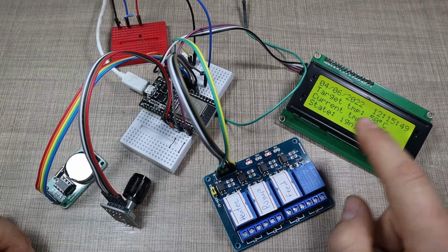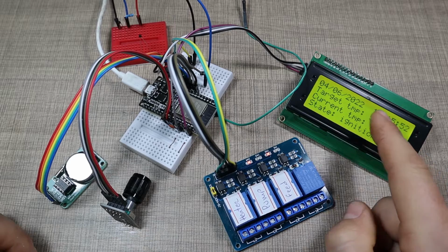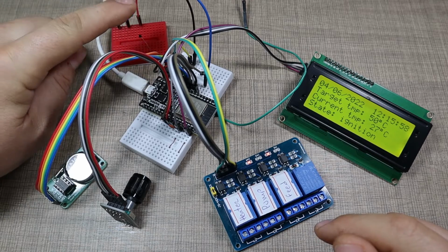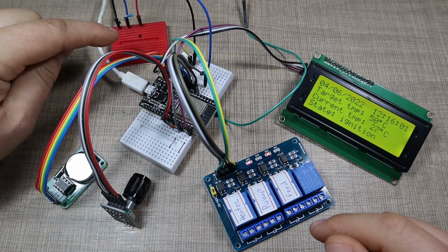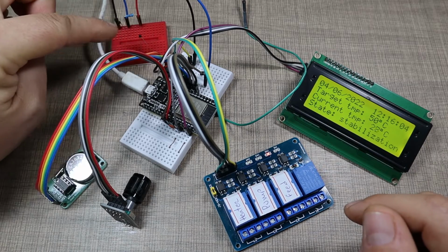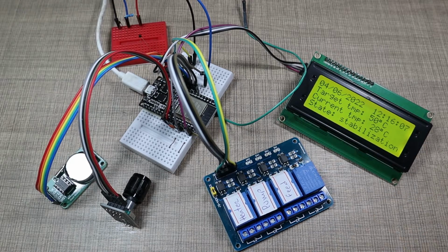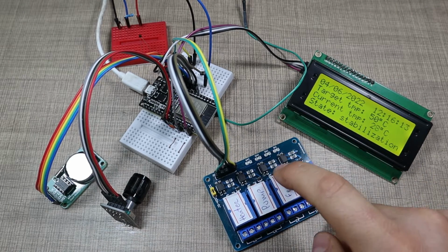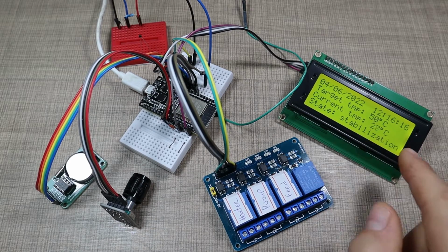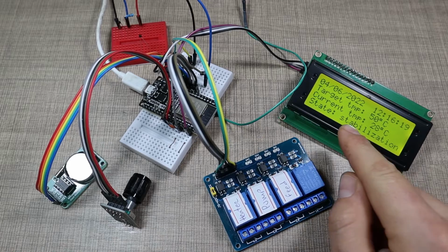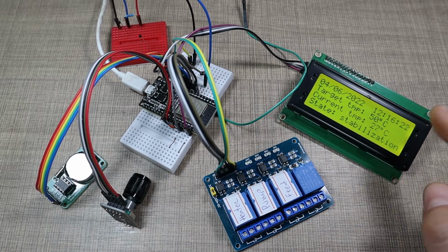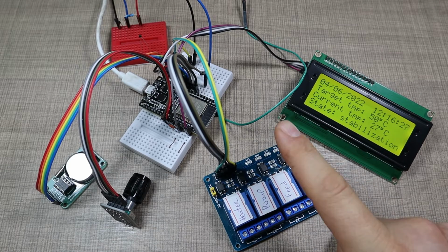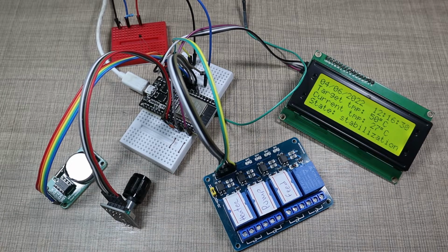So during the ignition time, the feeder will work for the set period of time, and then we'll have the heater. Ideally, we will also have a check for the temperature of the exhaust gases coming out of the heater, and that would control the period as well. Now we went into the stabilization mode, and during that mode, the feed relay will be turning on and off on a period as set on the controls. We had that set for, I think it was 30%. So in any 10 seconds, the feed relay will be on for 3 seconds if we have a 30% duty cycle.